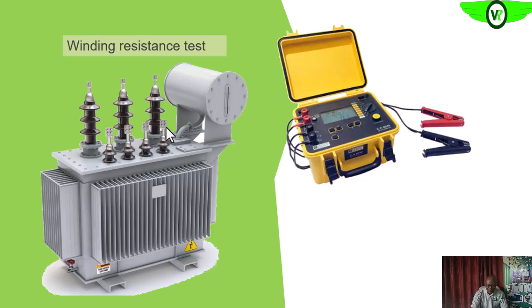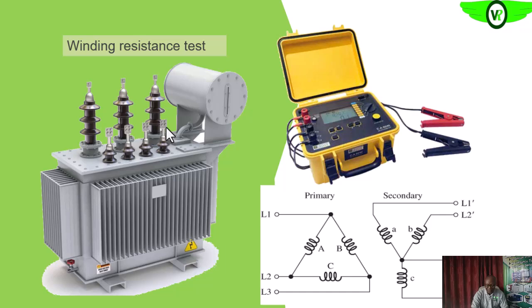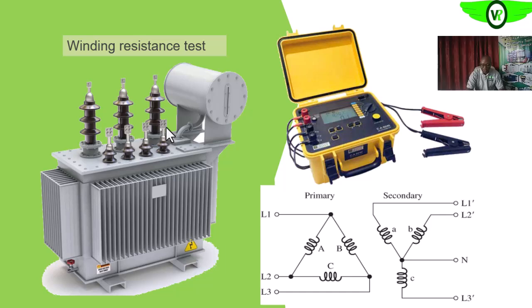You can also check the description below for a link to the winding resistance test on transformers and electric motors. The resistances of each of the windings on the primary side are expected to be the same. On the secondary side, they are expected to also be the same. If there are discrepancies, you want to do further investigation to determine why we have such discrepancies.